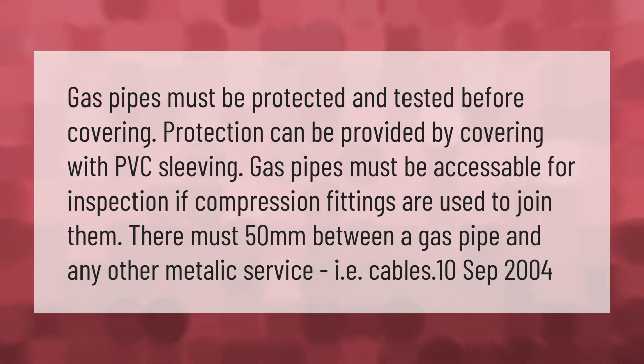Gas pipes must be protected and tested before covering. Protection can be provided by covering with PVC sleeving. Gas pipes must be accessible for inspection if compression fittings are used to join them. There must be 50 millimeters between a gas pipe and any other metallic service, such as cables.